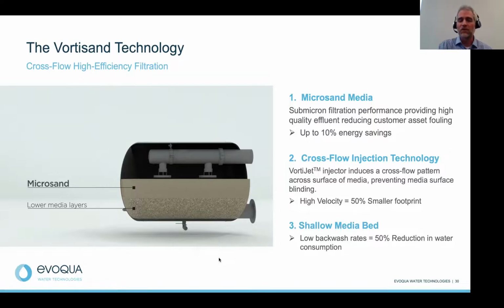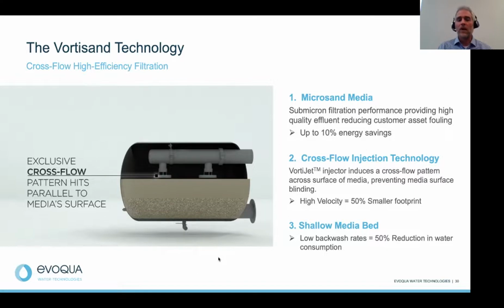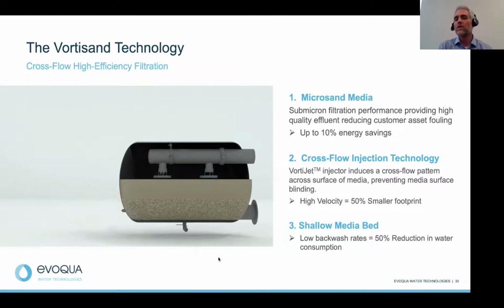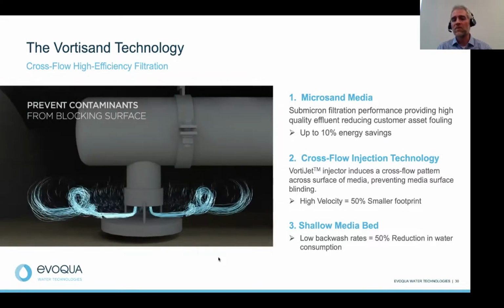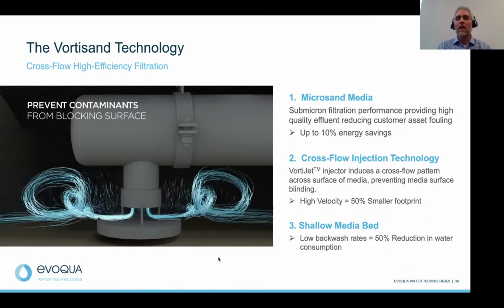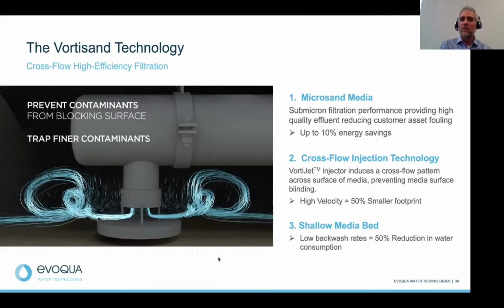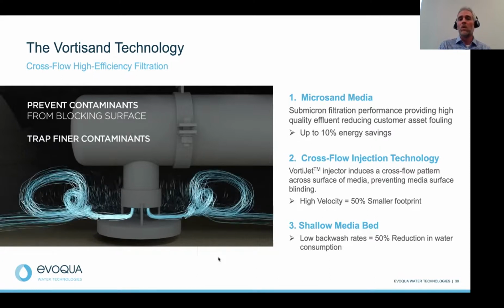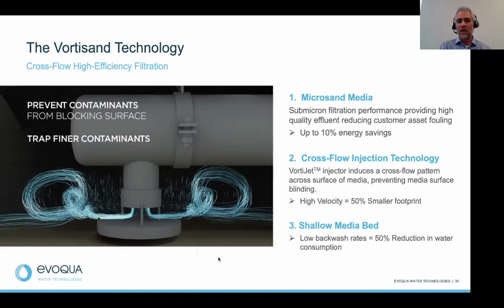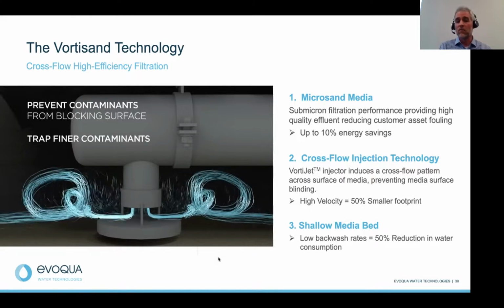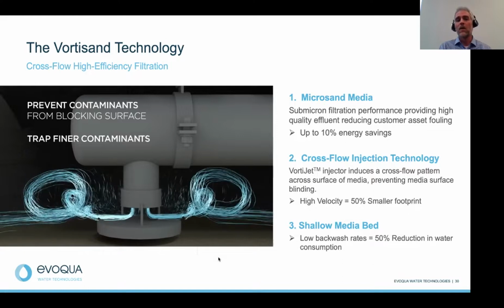media types of technologies. And when you look at the shallow bed, so we're using about 8 inches of media here. That actually reduces the overall backwash consumption, right? Shallower bed, smaller flow rate to fluidize and remove that solids particulate collected. So you're potentially able to save about 50% reduction in water consumption. But Vortisand is really combining the media, microsand, achieving submicron performance, with the crossflow injection allows you to do submicron performance at high velocity, something really unique within the industry, ultimately impacting various different cooling systems at a high level.